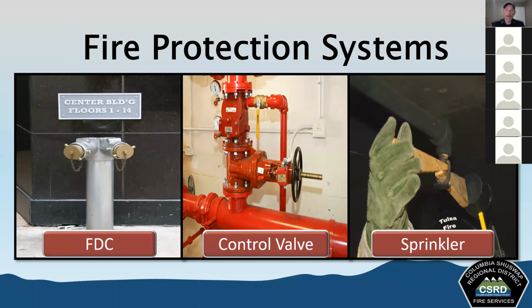Basically, once the fire is under control in a protected structure, we need to shut those sprinklers off. That may include using things like wooden wedges, and the technique being shown in the picture on the right is a great technique: using two wedges, crossing them over, it pushes the sprinkler head up and stops the flow of water. There are other techniques besides the wedges, and you can use things like sprinkler tongs, and there is a sprinkler stopper as well.